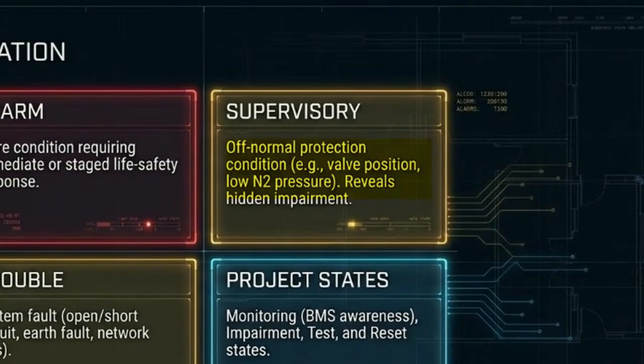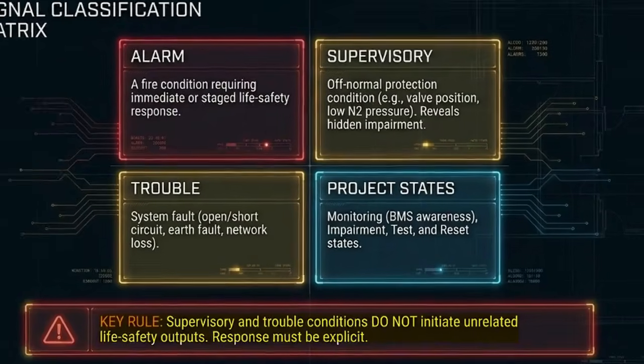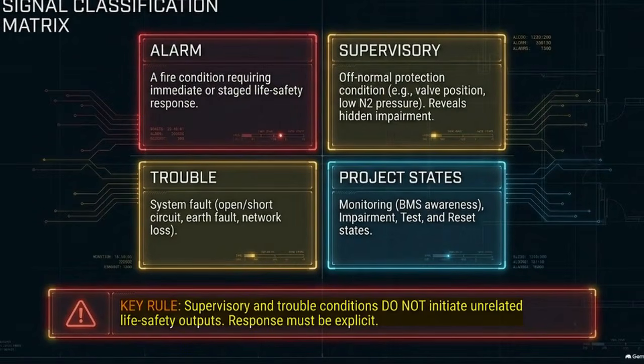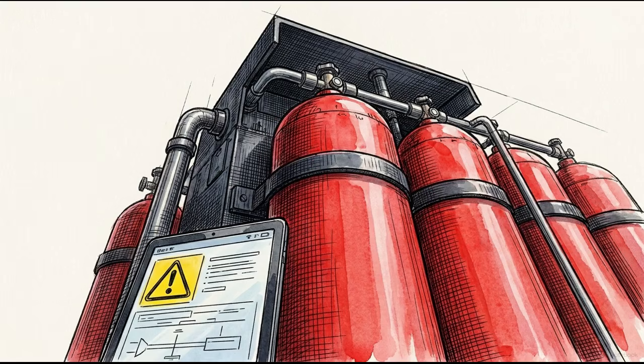Supervisory signals reveal off-normal conditions, like closed valves, demanding urgent maintenance escalation. They do not, under any circumstances, cross the firewall to initiate unrelated life safety evacuations. By explicitly classifying inputs, the matrix ensures that a maintenance alert lacking life safety authority cannot cross the firewall and accidentally trigger a multi-million-dollar suppression dump.